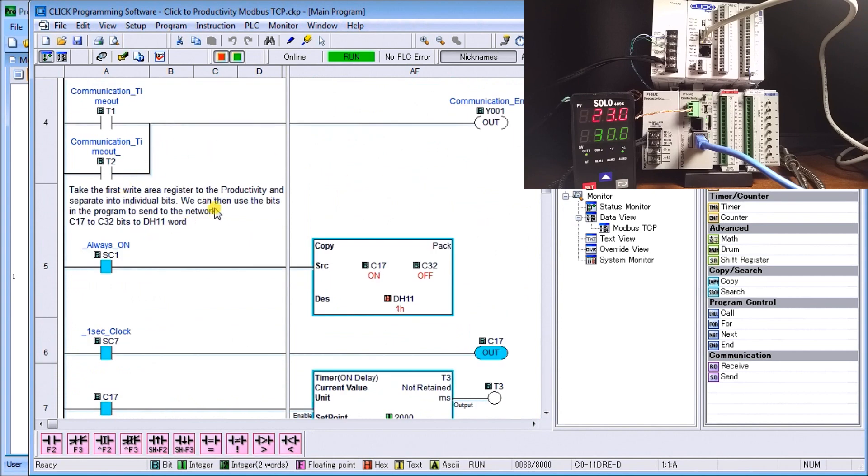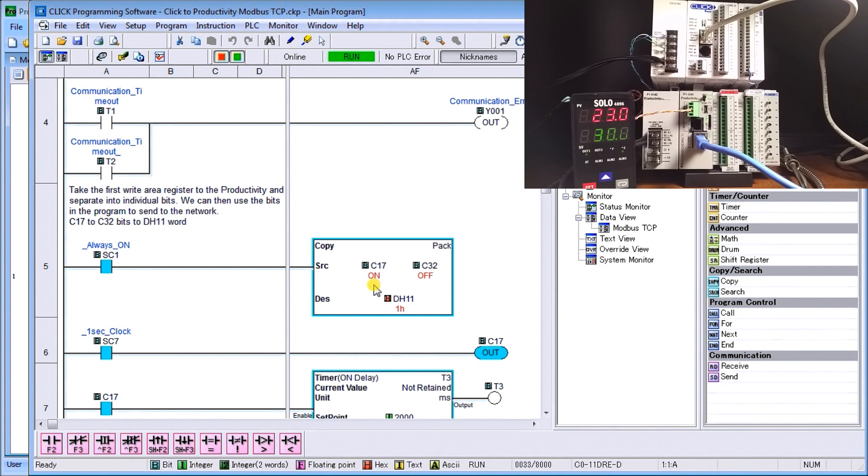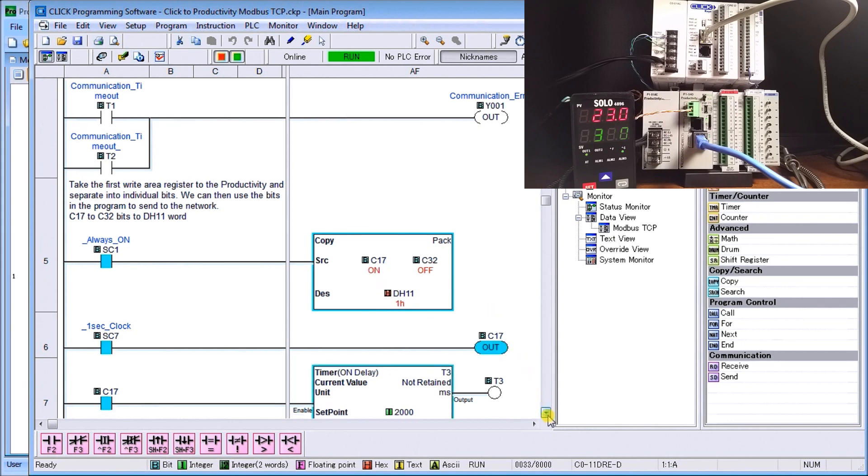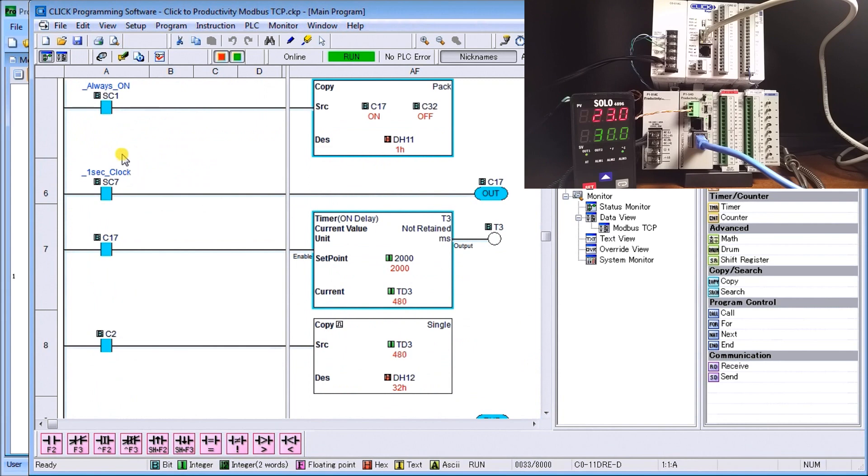The next one that we're going to do is actually time how long it takes for the information to get back and forth. In our case here, we have Always On and we're actually unpacking the bits, or packing up the bits from C17 to C32 into DH11. We use the one-second clock pulse to toggle C17 on and off, and when we have C17 on it starts a timer.